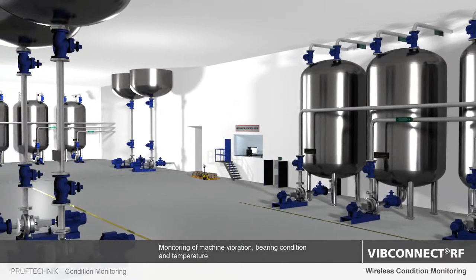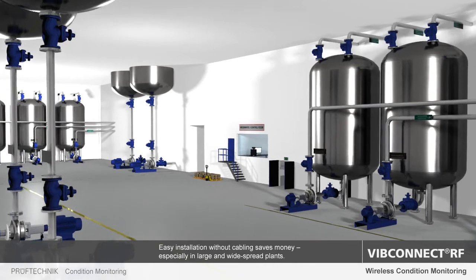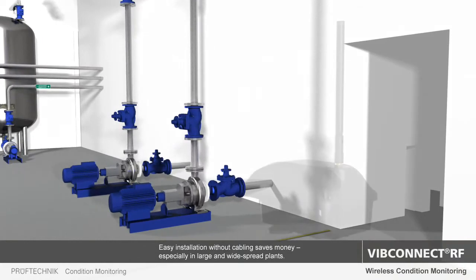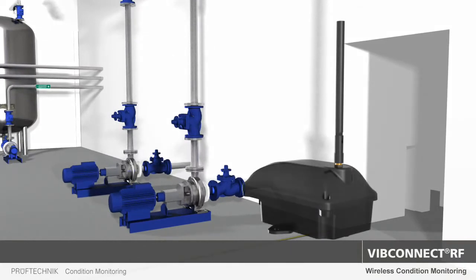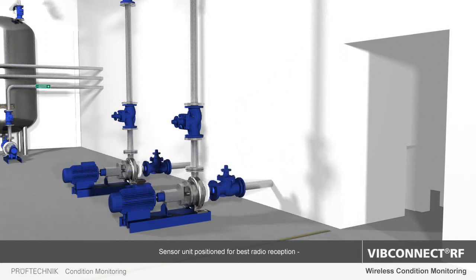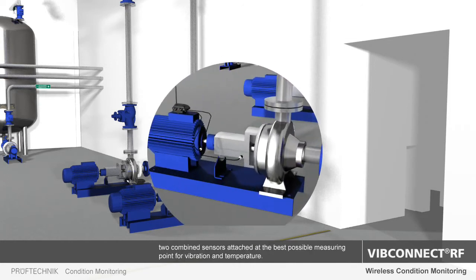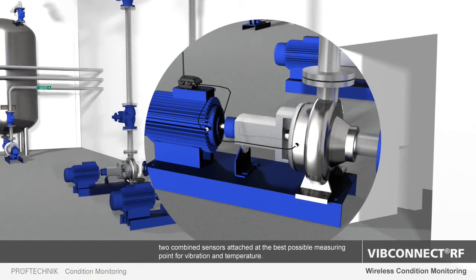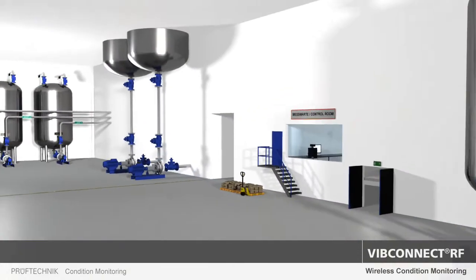Using the VibConnect RF system, you can now also monitor plants that extend over a large area without the need for costly cabling. This can be achieved by simply installing a sensor unit consisting of a radio module and two combined sensors for vibration and temperature at the machines. These devices can be powered by long-life lithium batteries, an energy harvester, or a 24V power source.